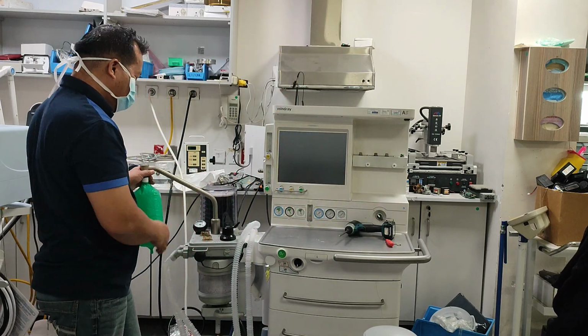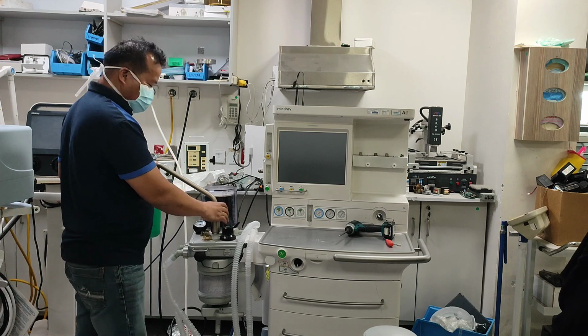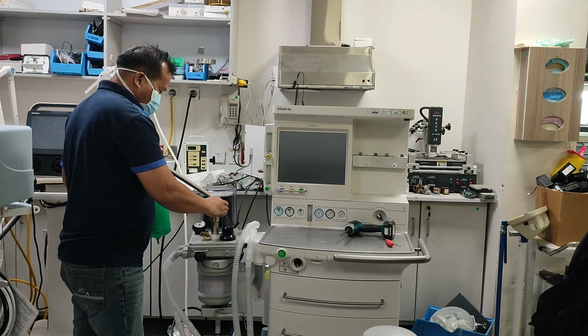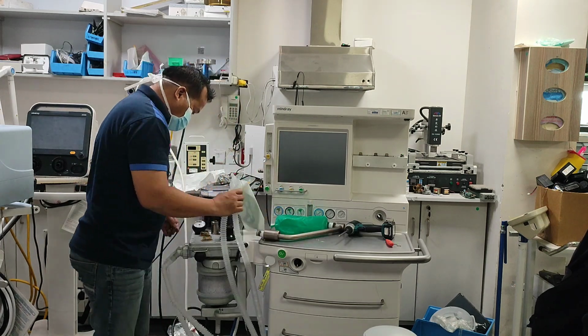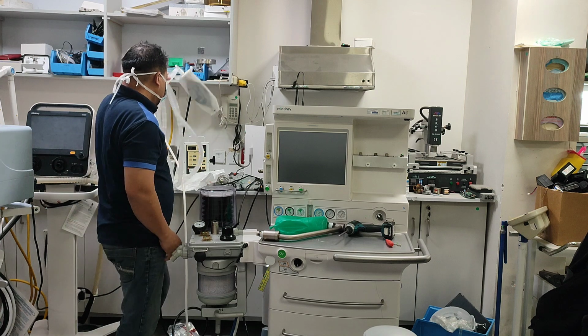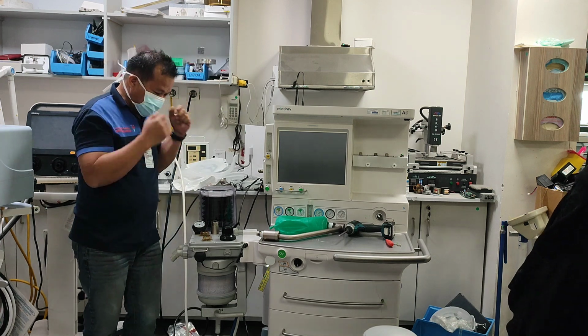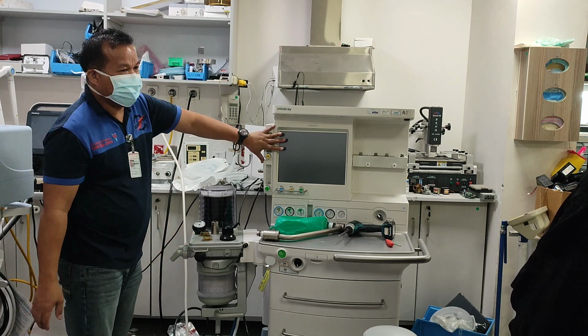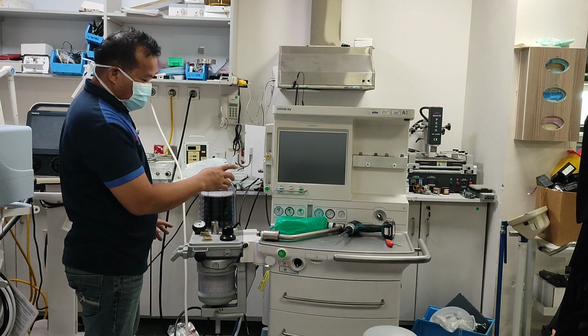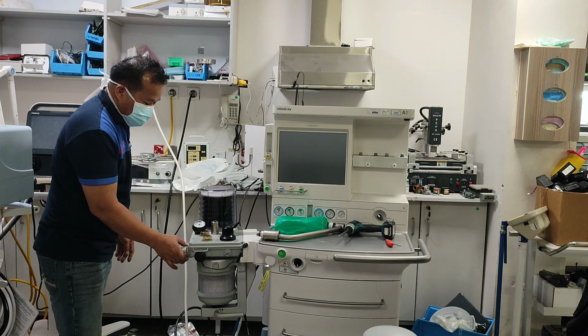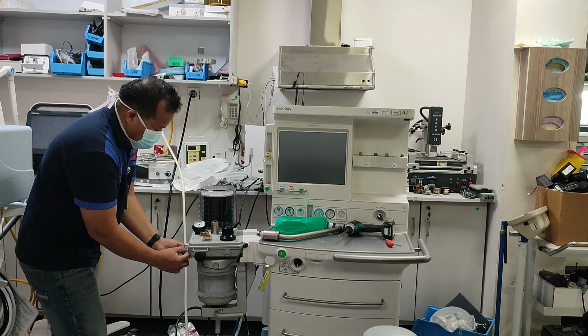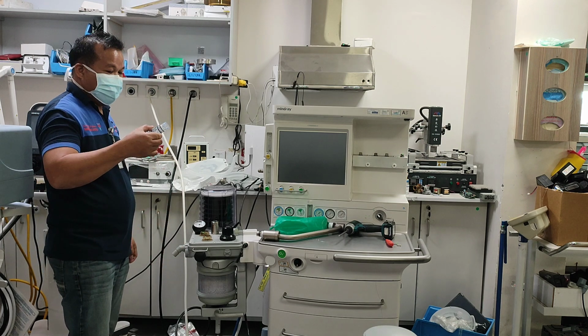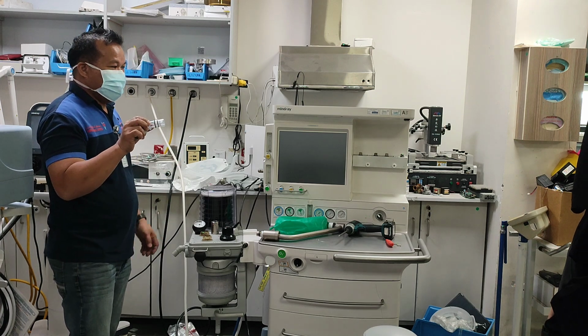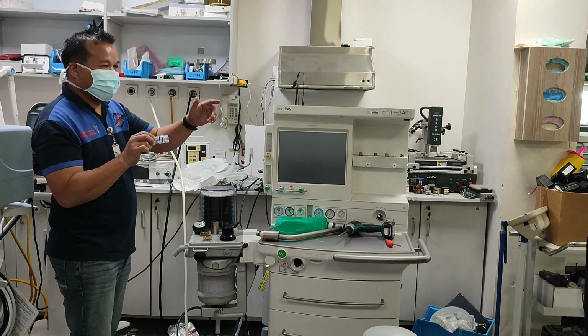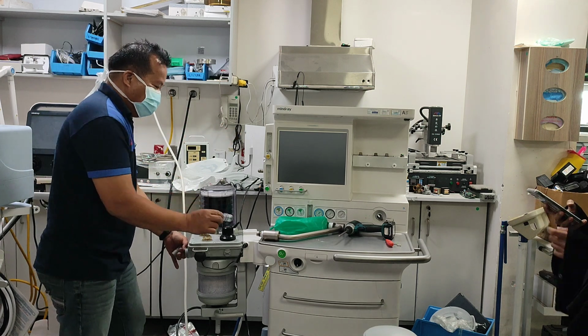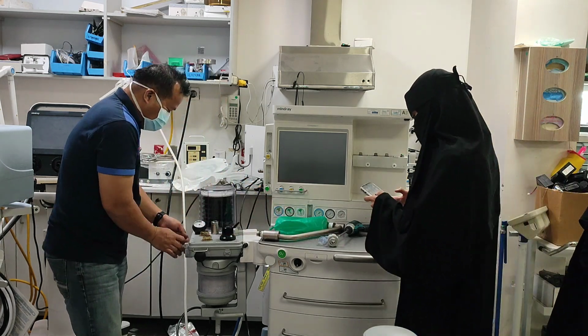Very important here is how to remove this one. Removing it is easy: just open the bag and remove. Here, if you see the tidal volume is not accurate, you can do a calibration. If you are doing the calibration, you will see there are two pressure sensors. This is the flow sensor. It detects the flow going to the patient. This is inspired, and this is expired.